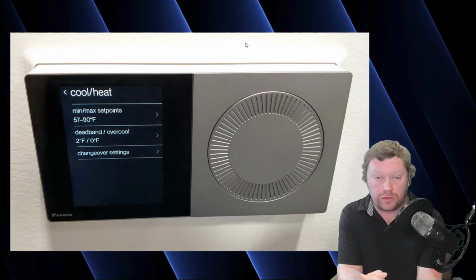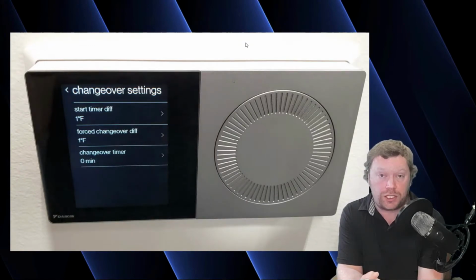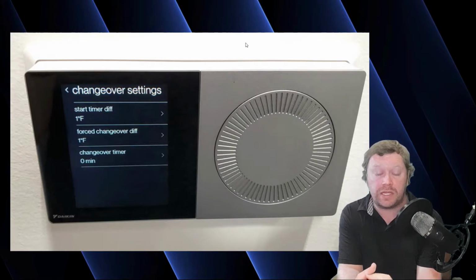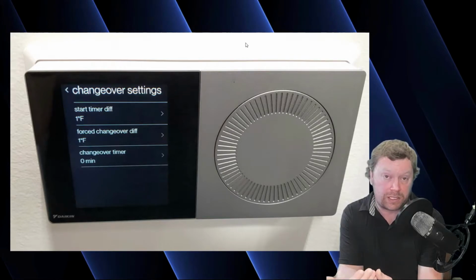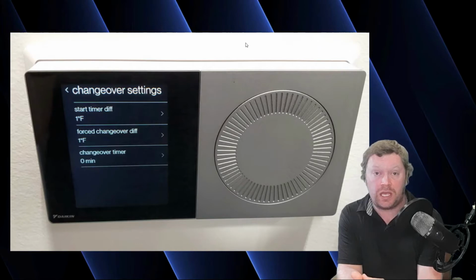So then you have your changeover settings. This is when your mode of operation changes from heating to cooling or from cooling to heating when you have it in the auto mode. So if you take our example of heat set point to 70 and a cool set point to 72, the out of the box changeover differential is 1 degree, which means if you're in heating, you're heating to 70, and the room has satisfied, but the sun has come out, it's in the early afternoon, and now your room temperature is 72. Because your cooling set point is 72, nothing happens. But if the room temperature gets 1 degree past 72, so 73 in this case, it starts what's called the timer.